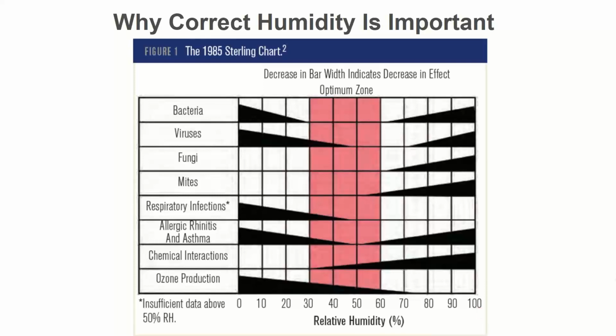Two different ASHRAE standards reference maximums for humidity. I forget which one says which, but ASHRAE 62.1, which I already told you is the indoor air quality standard, and ASHRAE Standard 55, which is human thermal comfort, both have limits for maximum amount of moisture. I forget which is which, but one of them says 65%, one of them says 60%, and the reason I keep forgetting which one is which is because I honestly don't care. If one says the max is 65 and the other one says the max is 60, I just roll with the lower one and then I'm covered for both.